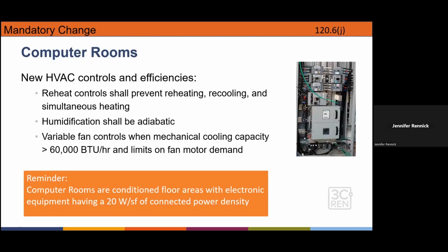For the computer rooms, and computer rooms are defined as conditioned floor area with any of the electronic equipment having a 20 watt per square foot of connected power density load or higher, the equipment that cools these computer rooms now has specific controls for not allowing reheat, and energy efficiency and capacity limits on the motor demand.